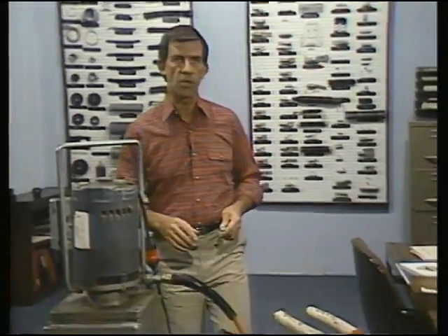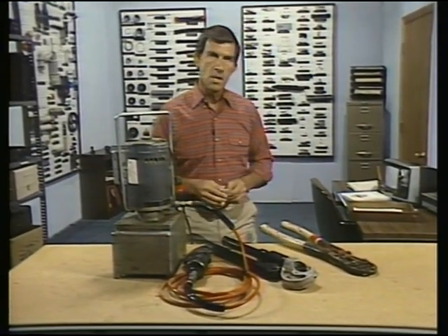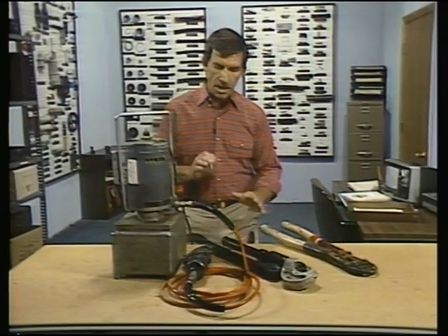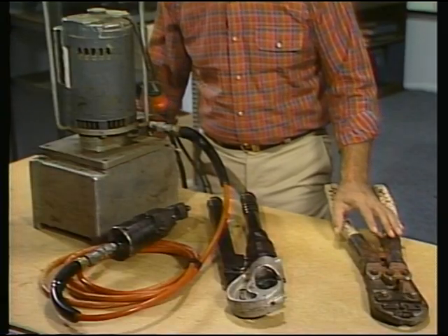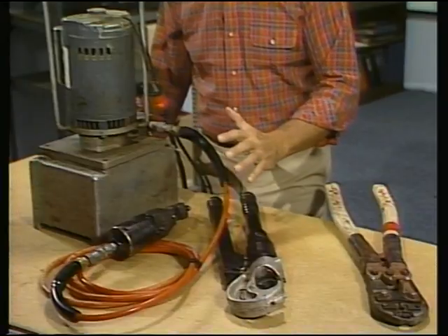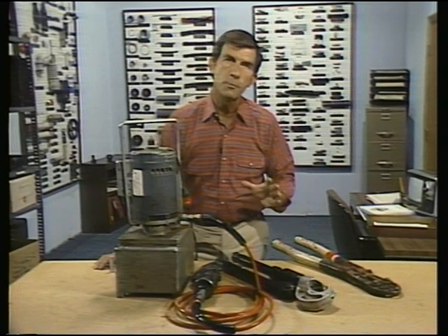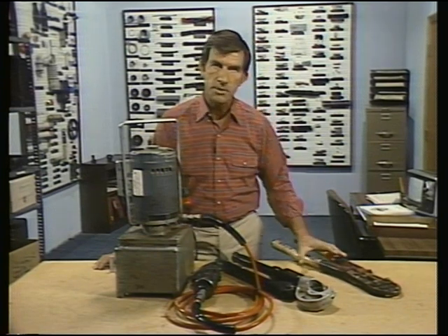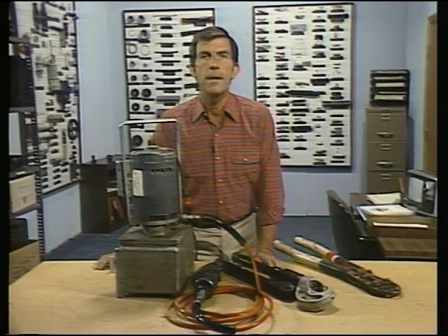Now, before we see the splice made, let's take a look at a couple of the tools used to apply the compression connectors. Two of the most common types of application tools or presses are the mechanical press and the hydraulic press. Mechanical presses use the mechanical advantage of their handles to apply pressure to the connector, while the hydraulic presses use hydraulic pressure. Generally, the size of the compression connector determines which type of press will be used.